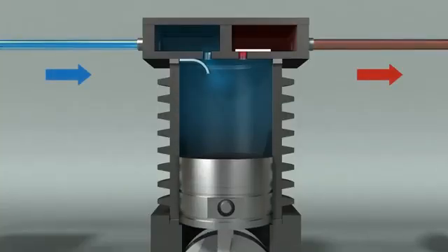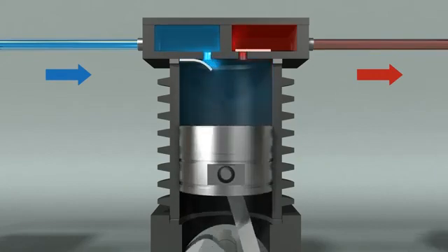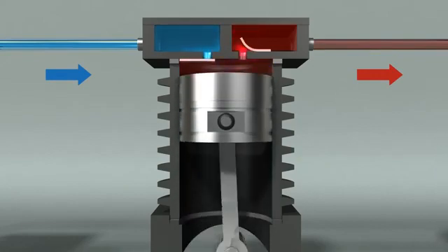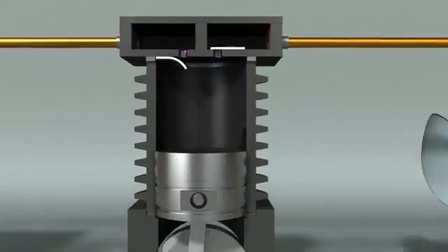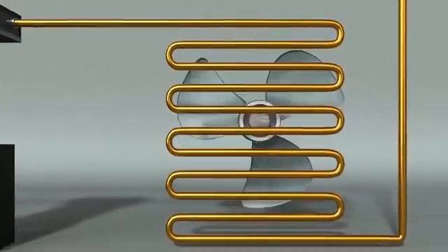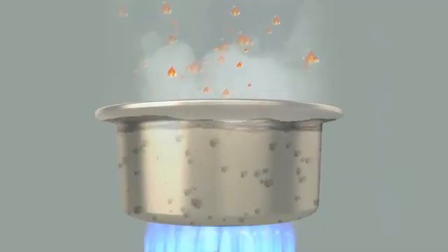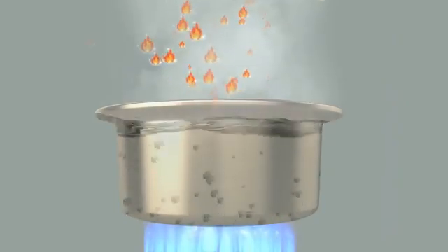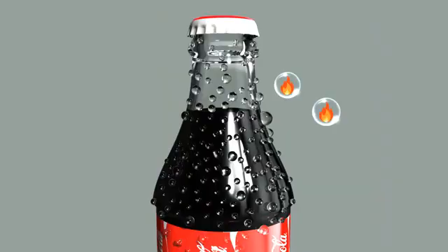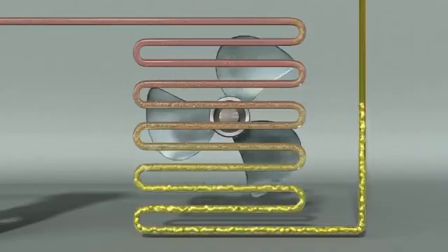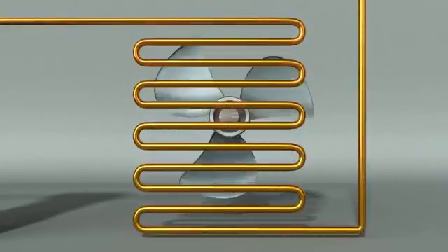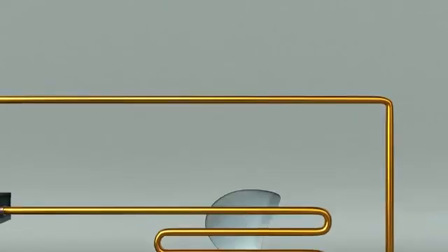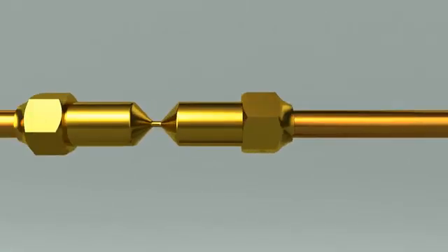This is a compressor. If we compare a refrigerant to blood, a compressor is like the heart. A compressor circulates a refrigerant and compresses it to high temperature and pressure. Then, the refrigerant pressed by the compressor flows to a condenser. While evaporation is the transition of liquid to gas through heat absorption, condensation is the transition of gas to liquid when it loses heat. A condenser serves to turn refrigerant in a hot gas state into liquid form by taking away its heat.